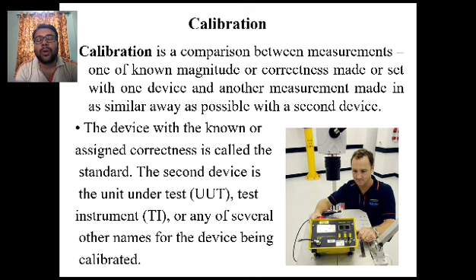The second device is the unit under test, or test instrument. Whatever devices we take as standards are classified apart from the UUT, the test instrument. The calibrated instruments are going to play a role as the reference. With reference to them, we are going to remove the errors and calibrate the instruments. Before calibrating instruments, we will see some important aspects of measuring devices.